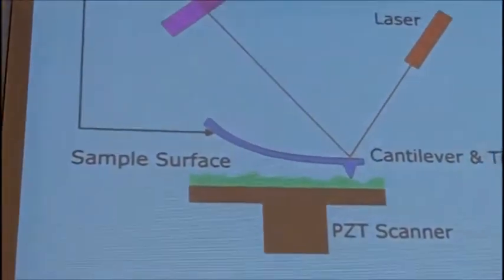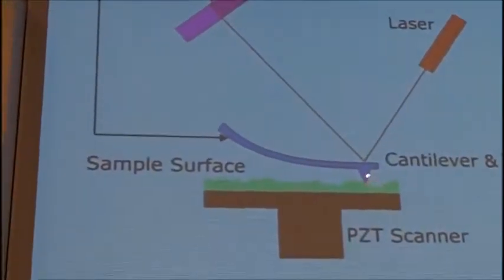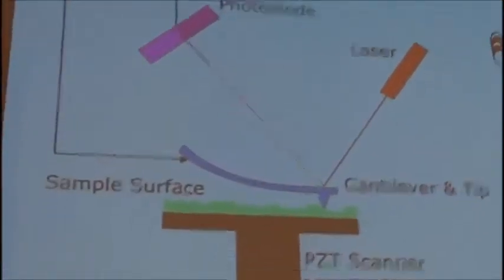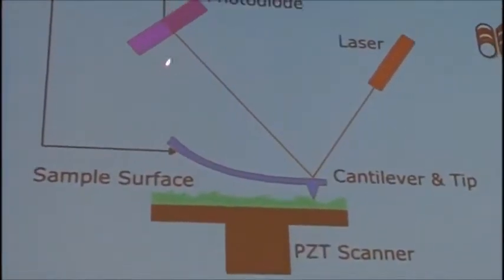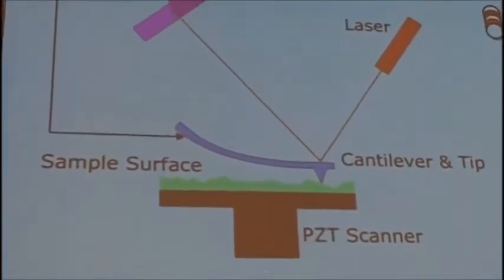Now how does that help us to get a better resolution? The tip has a very, very small diameter at the bottom, typically something like 10 nanometers or even less, so our resolution can become really 10 or even 5 nanometers in the spatial resolution. So what happens next? We have here the tip touching the sample, and we know that it is very close to the sample because the laser deflected a little bit up.